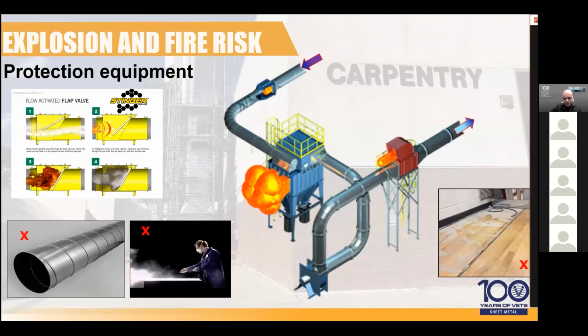So if you go see a client and you see a collector, the first step is to know if your dust is explosive or not. The first step is essentially to collect a sample of dust. Generally, I recommend collecting it in a barrel and sending it to a lab, and the lab will characterize the explosibility of the dust. They'll have a ball where they blow up different concentrations of dust with different igniters, and that will generate essentially enough data to characterize that dust.